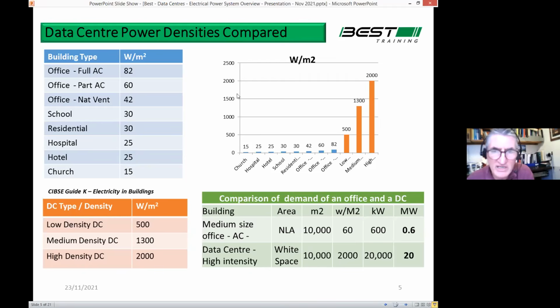Now, if you look at that, I've just thrown those into the data center ones. Then I've shown down the end low, medium, and high density, 500 watts per square meter up to 2,000 watts per square meter. If you throw that into the graph, you can see the difference. So a high intensity data center is 2 kilowatts per square meter, not 2 megawatts. 2 kilowatts per square meter.